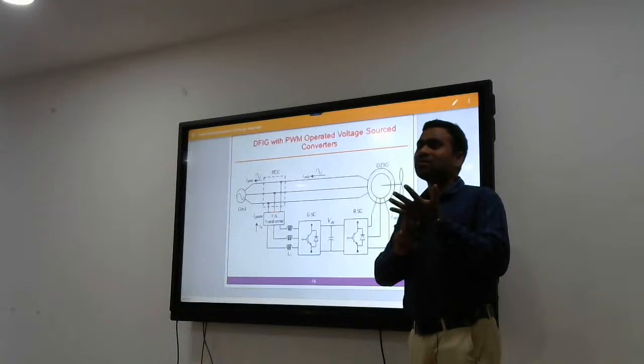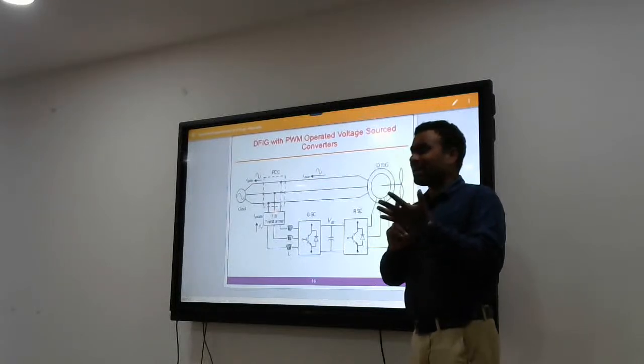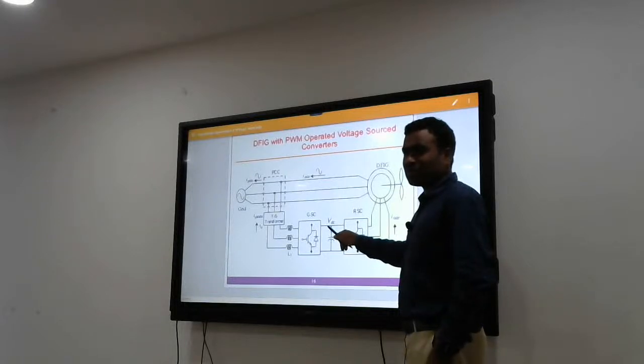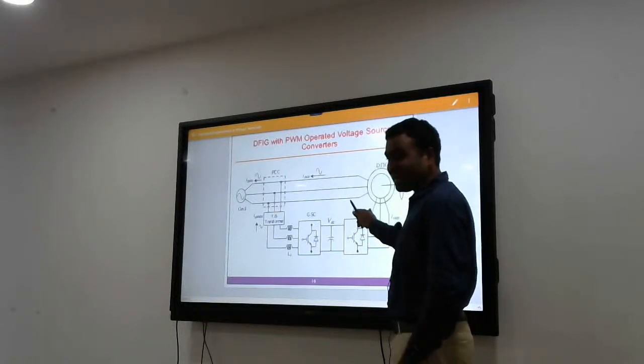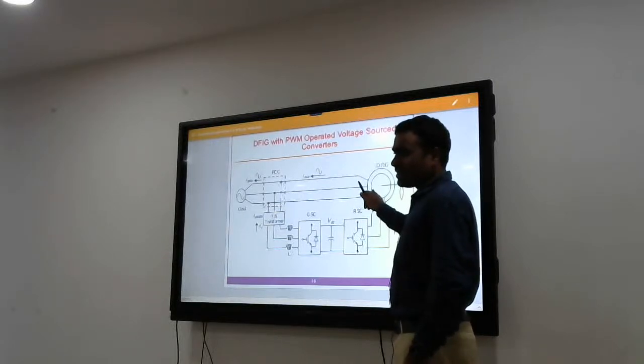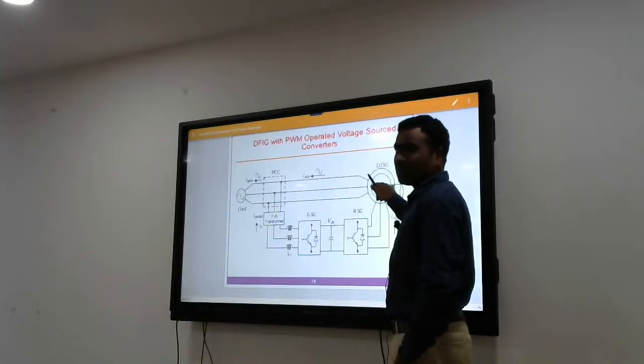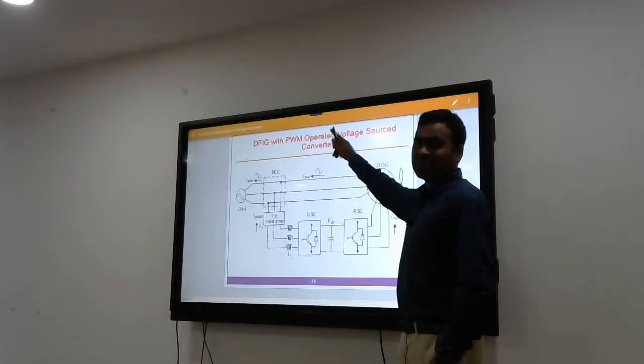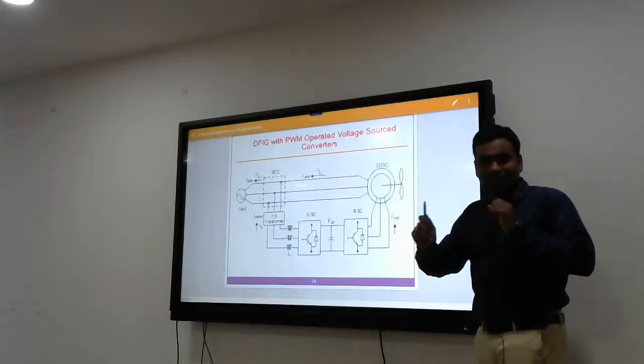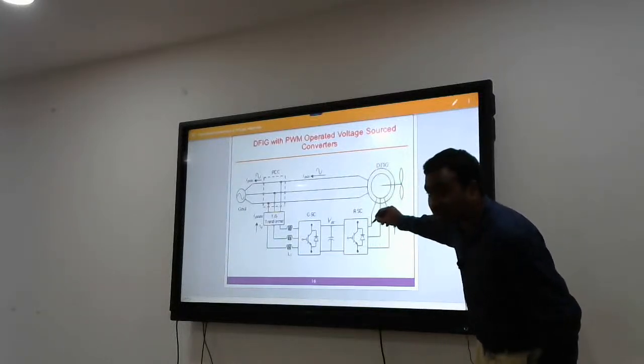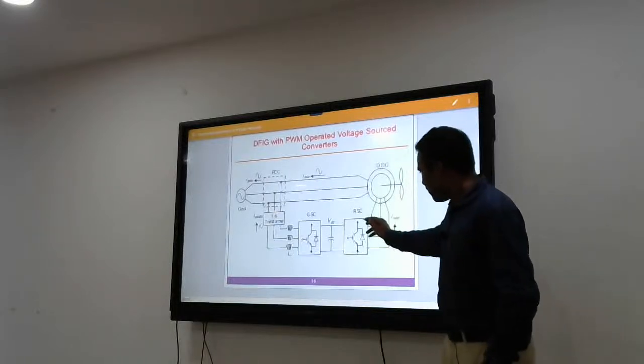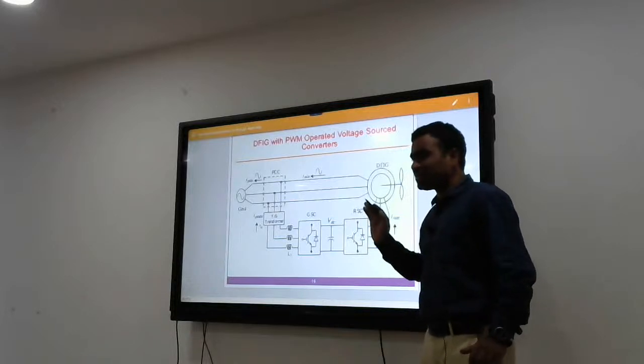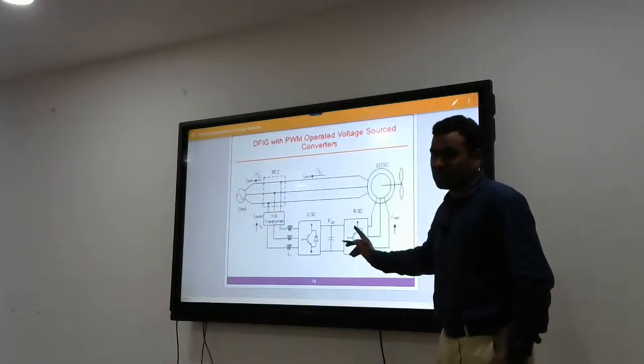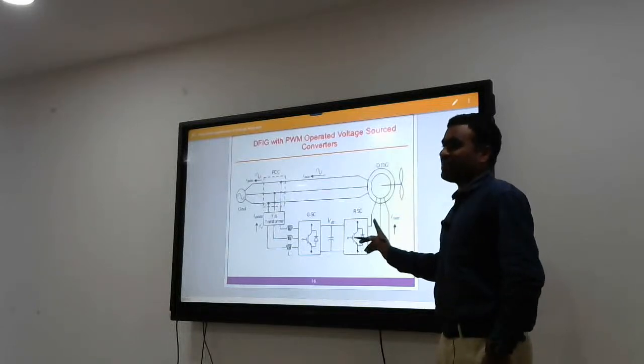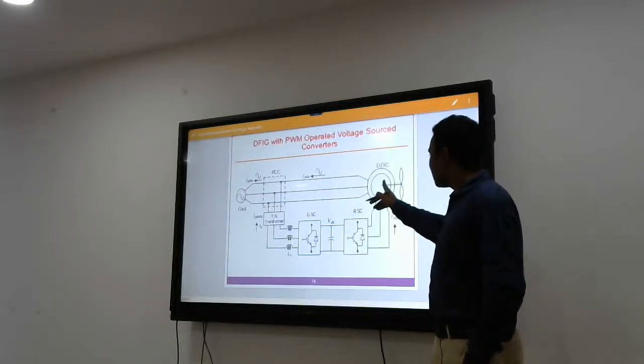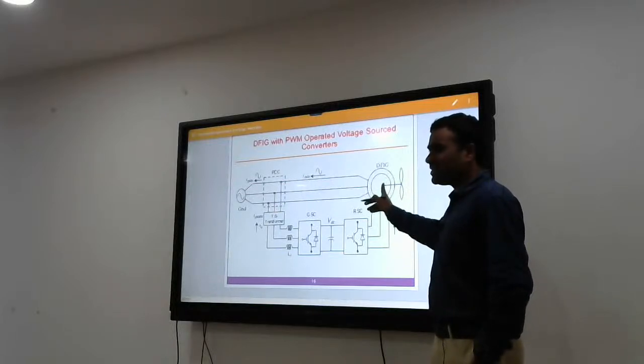For changing speed, you have to change the electrical power. That electrical power will be changed with the help of this rotor side converter. So with the help of this rotor side converter, this rotor current, I will change the electrical power, and that electrical power will change the rotor speed, and rotor speed will in turn change the MPPT point. Yes, okay. So all this rotor current will be controlled with the help of this rotor side converter. So by this maybe we can understand this rotor side converter is responsible for achieving maximum work. By controlling the current here, the active power is changing, and by that the mechanical speed is changing, and by that MPPT is changing.